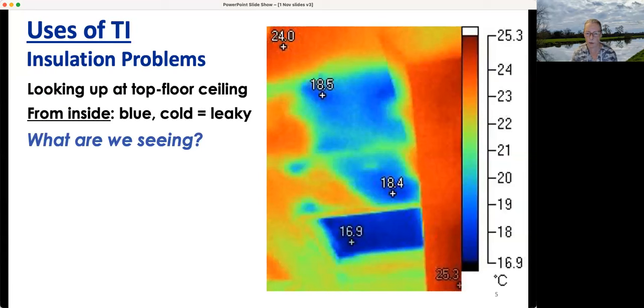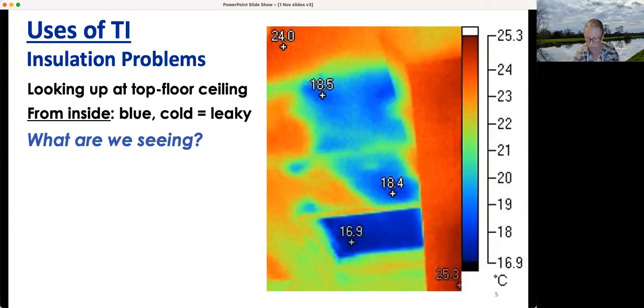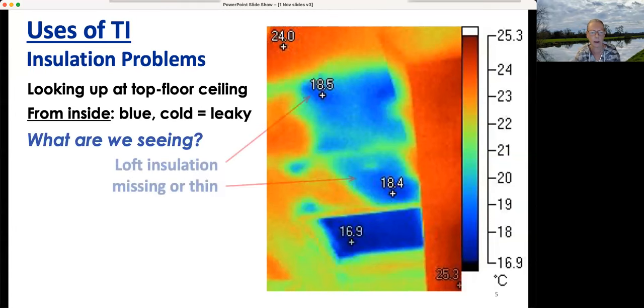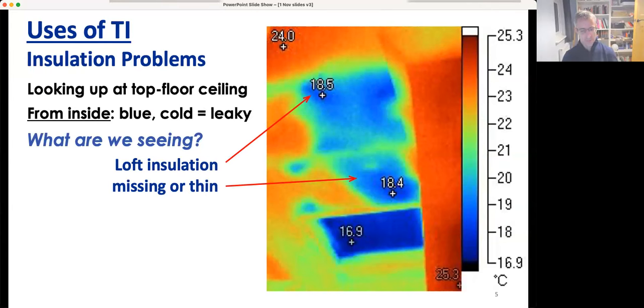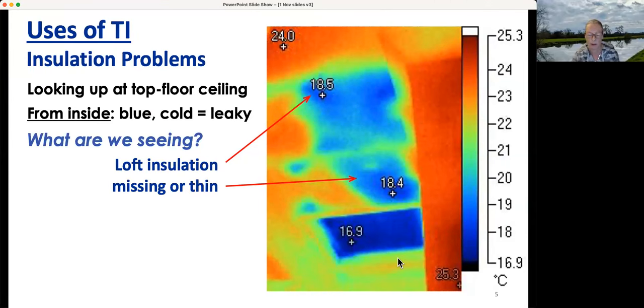Here we've got a picture looking up at the top floor ceiling — behind that surface is the loft. If things are cold, it means they're losing heat to the outside. What you're seeing is missing loft insulation, primarily. This darker area? Probably a loft hatch that's not insulated — that's quite bad.